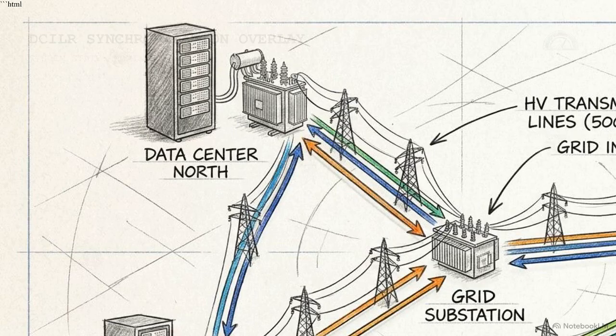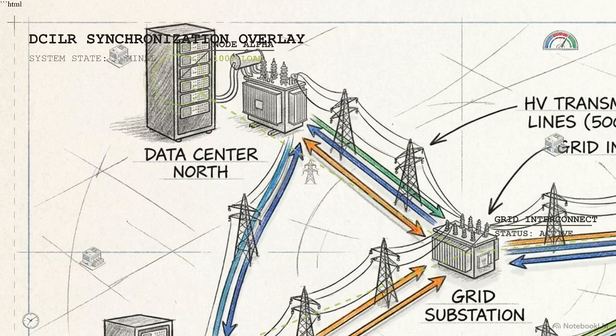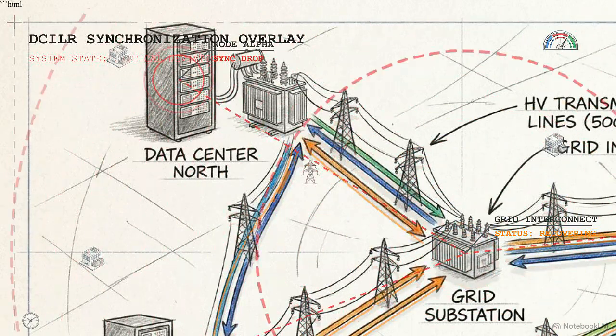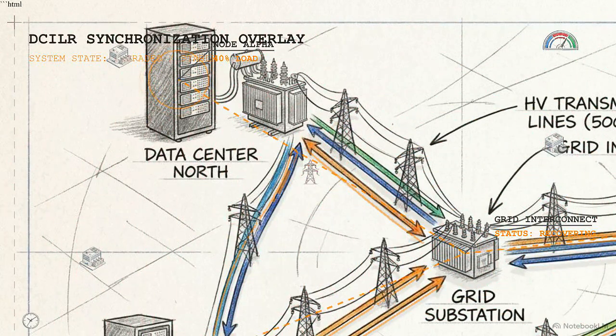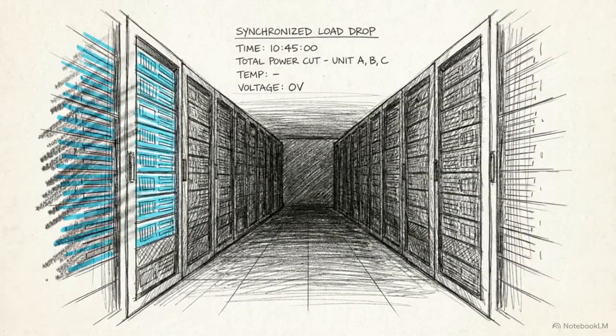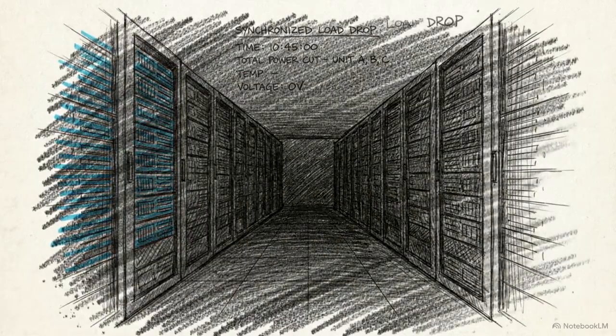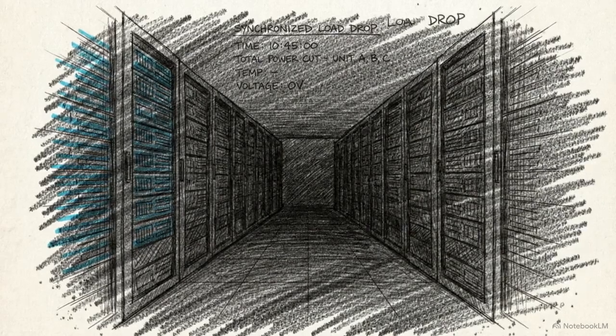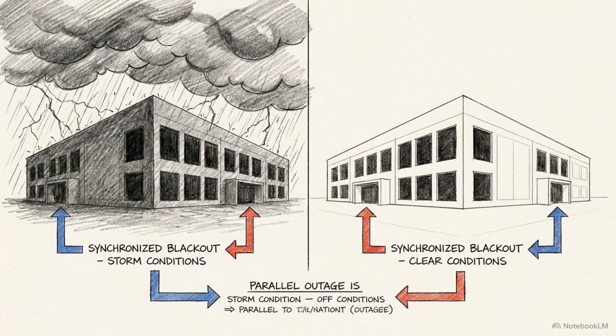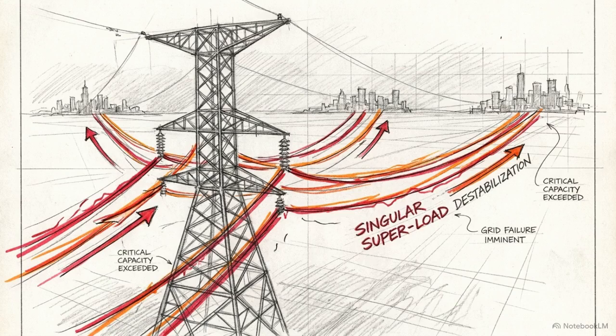This map shows shared AI training connecting separated data centers. If a lightning fault strikes one node, power across all 3 facilities instantly drops to 0. The synchronized loss of hundreds of megawatts shocks the grid, triggering frequency deviation warnings. Because the AI workload is parallelized, an interruption at one facility forces all participating facilities to immediately halt their processes and drop their load in unison, even if those other sites experienced no electrical disturbance. Distributed training turns separate facilities into a singular superload, allowing a localized fault to destabilize the grid from hundreds of miles away.